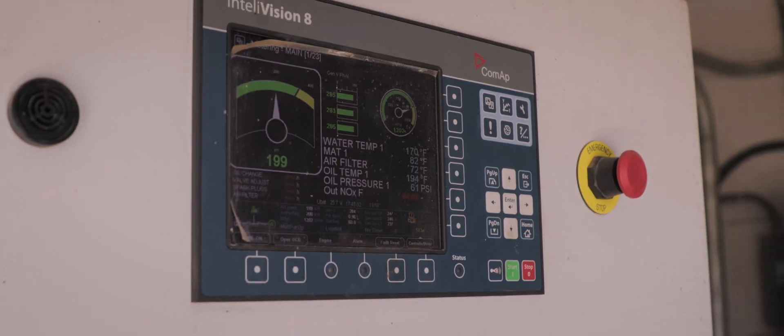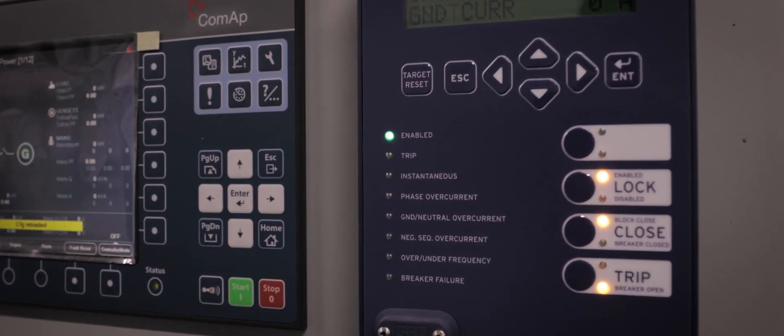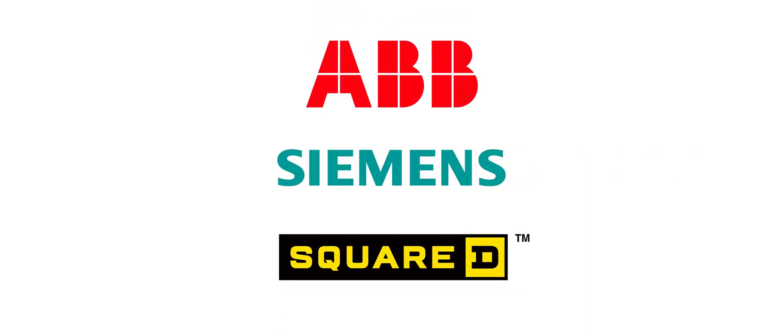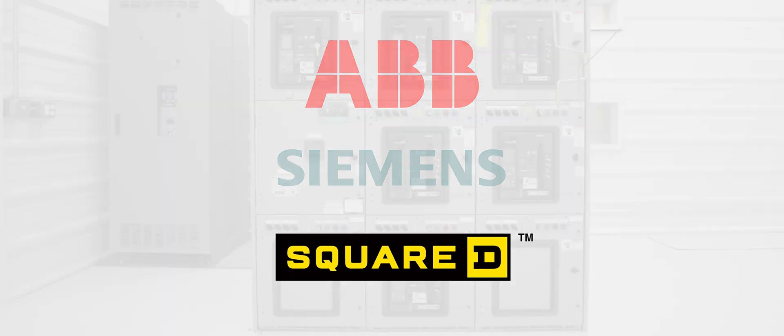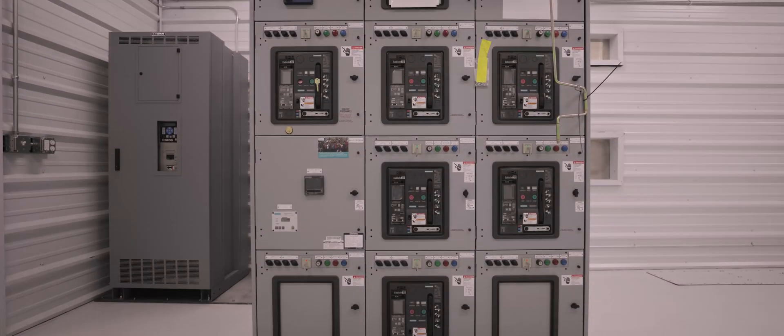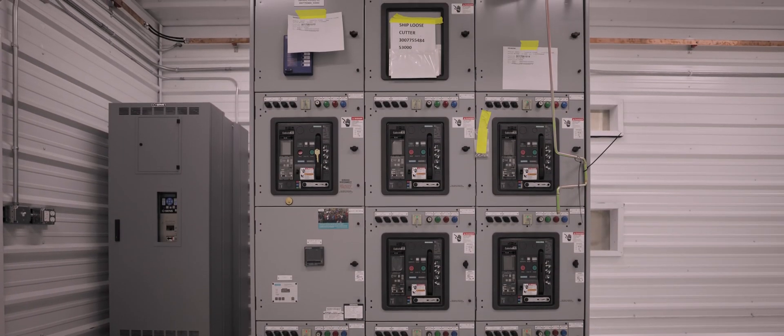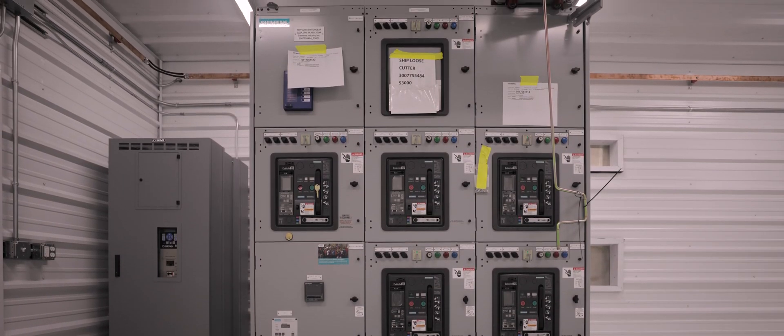The generator control package will also take care of all the paralleling capabilities of the engine. A key component to the power generation system is the generator circuit breaker. Martin Energy Group buys name brand breakers such as Siemens, ABB, or Square D in a cradle, and we install it in a custom cabinet and connect it to the generator.